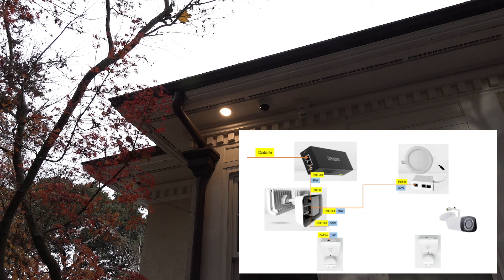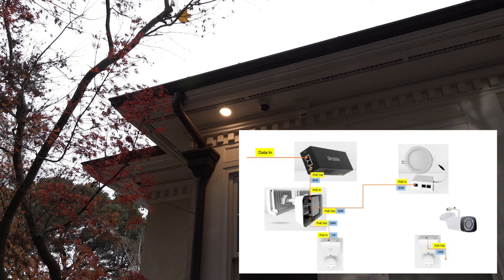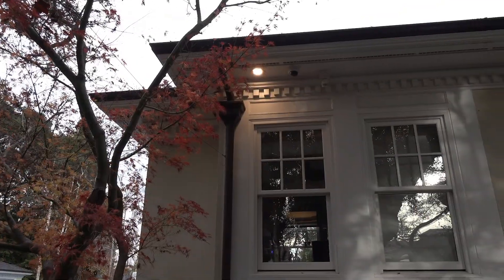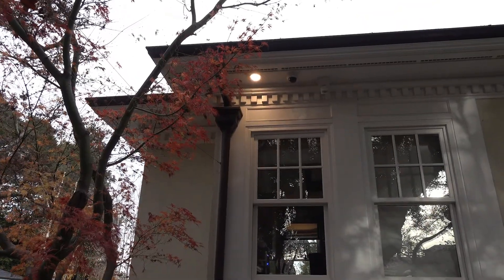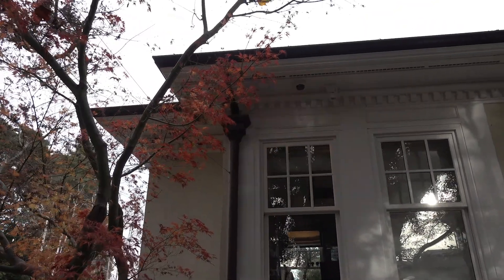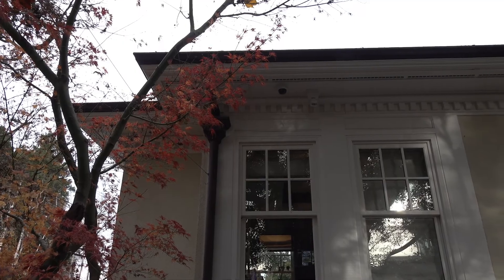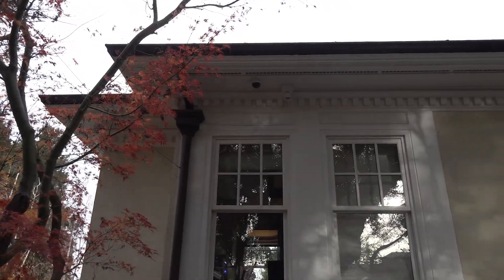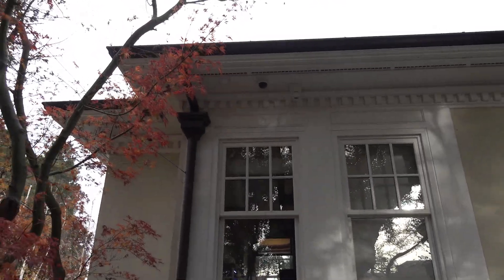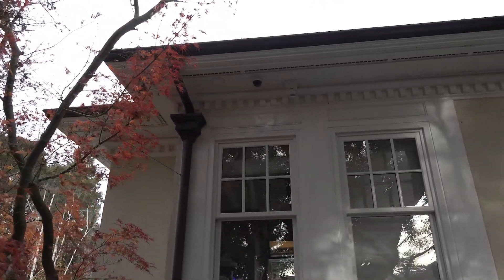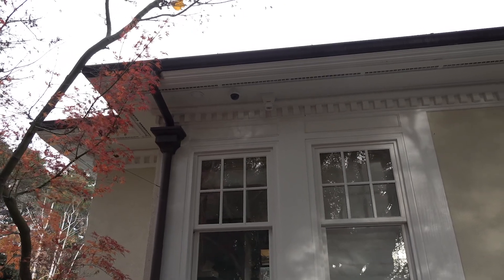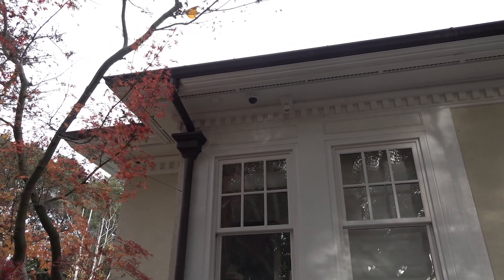It is supplying that camera which consumes about six watts and the second MD1 which uses less than one watt. The pass-through feature on these lights gives you a lot of flexibility, allowing you to place several MD1s and still have plenty of power left over for security cameras.